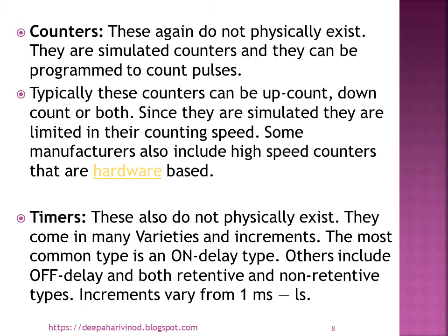Now counters. These again do not physically exist. They are simulated counters and they can be programmed to count pulses. Typically these counters can count up, count down, or both. Since they are simulated, they are limited in their counting speed. Some manufacturers also include high-speed counters that are hardware based.